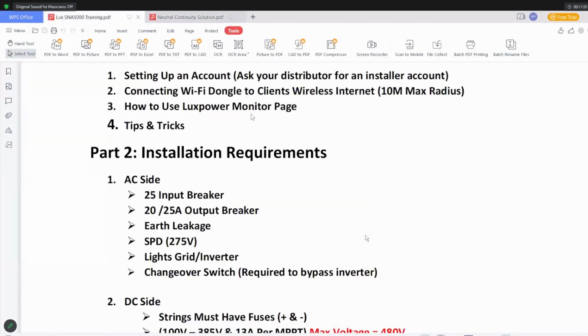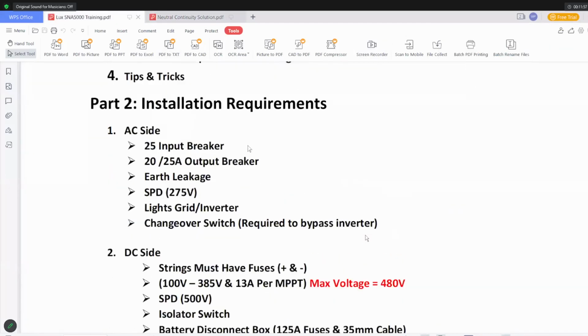All right, an SPD of 275 volts is recommended from the AC side. Lights for the grid on the inverter are basically to install lights that can indicate to the end user that the grid is on and is going through the Luxpower inverter. This is obviously if you're using it as a hybrid setup. A changeover switch is recommended for the bypass. This is extremely important if you guys want to do the firmware changes on the Luxpower inverter, as the client's household load needs to be running through Eskom and not through the inverter.